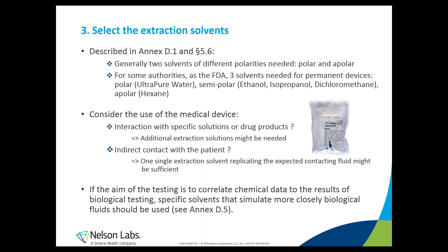You should also consider the use of your medical device. For example, if there is interaction with specific solutions or drug products, additional extraction solutions may be needed. If your device comes into indirect contact with the patient, one single extraction solvent replicating the expected contacting fluid might be sufficient. If your device will only be used with saline solution indirectly, there will be no need to extract it with an apolar solvent. If the aim is to correlate chemical data to biological testing results, specific solvents simulating biological fluids should be used, as given in Annex D.5.